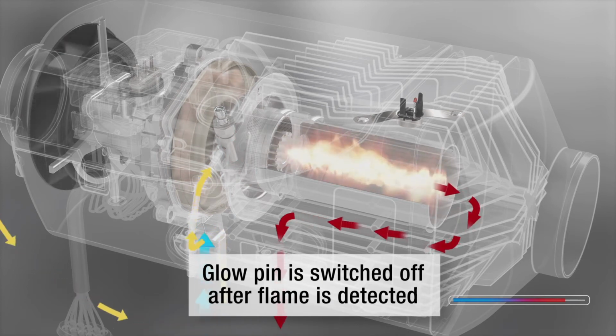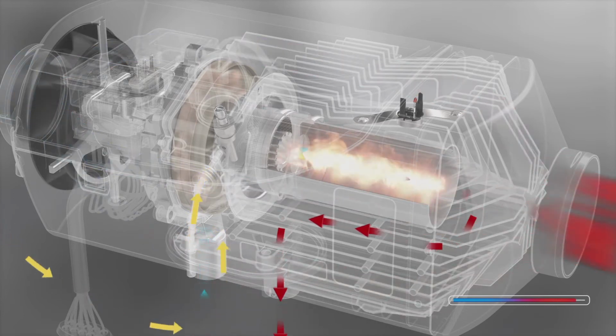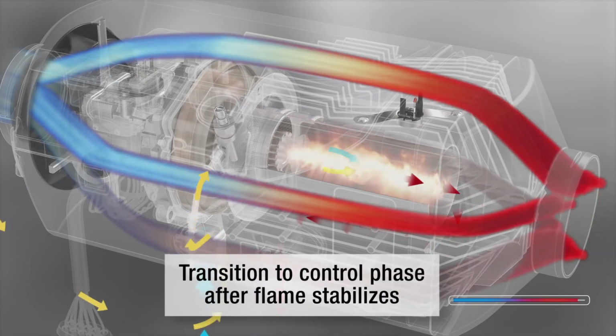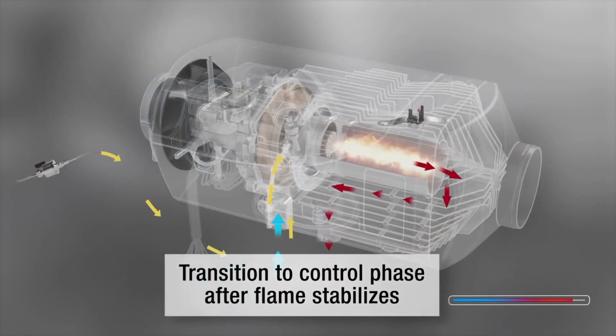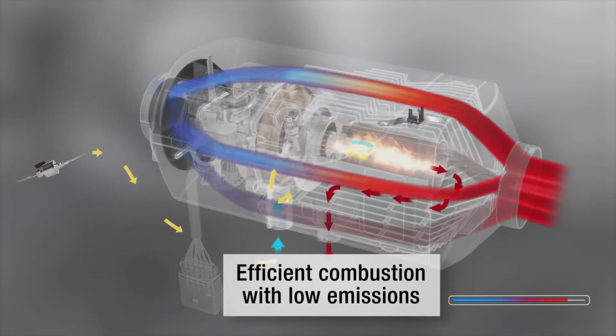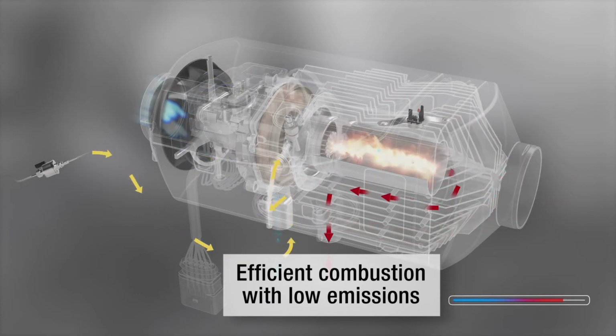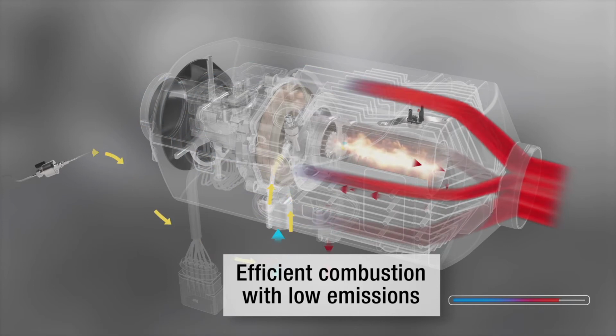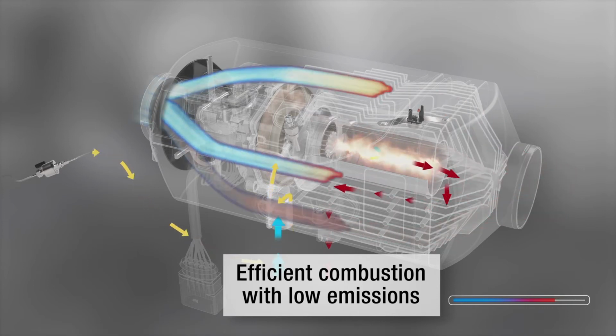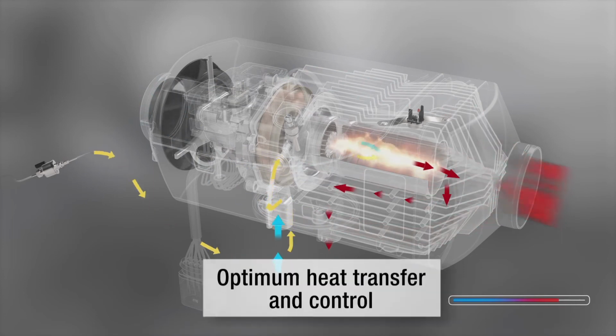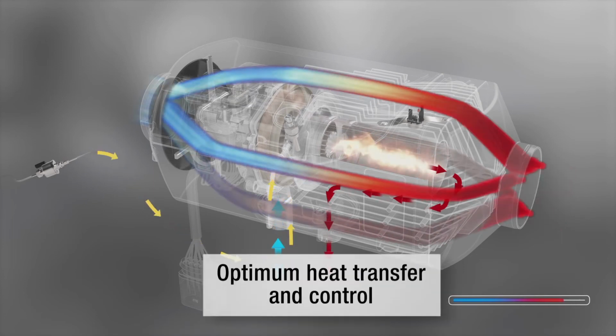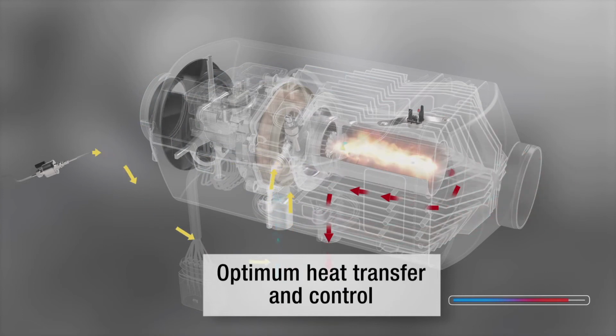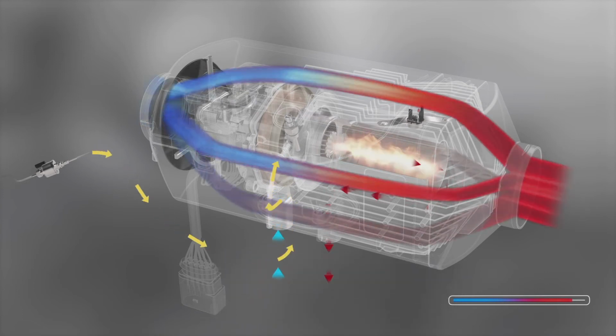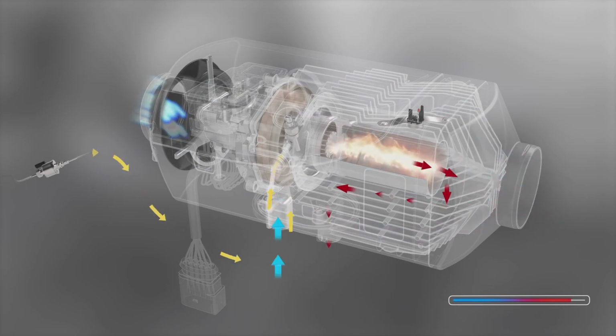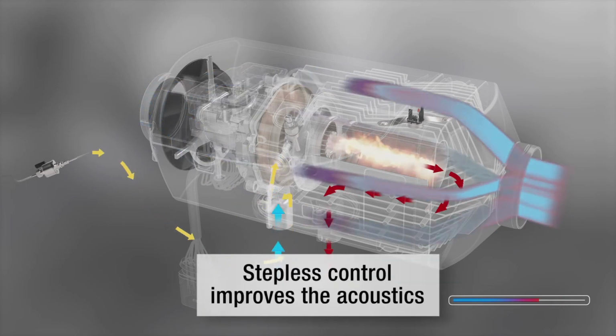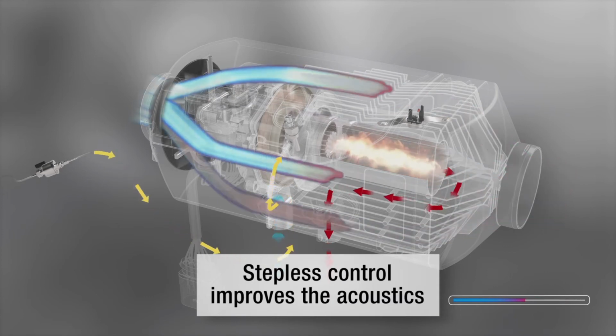Combustion is then powered up to the maximum level. Once the flame has stabilized, the heater switches to the control phase. For this, the temperature specification from the operating devices, the set point, is compared with the actual value as measured on the temperature sensor, and stepless adjustment of the heating performance takes place. The heating performance is adjusted proportionately via the delivery rate of the fuel metering pump and the speed of the fan motor. The stepless heating performance control reduces the heater's perceptible operating noise.